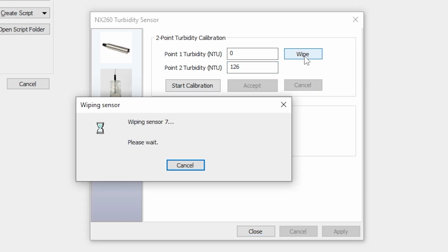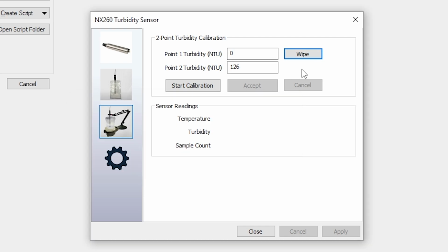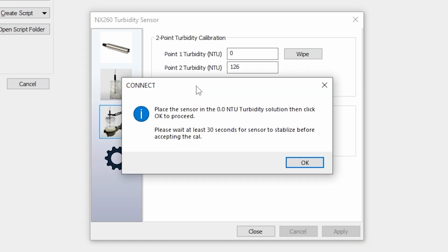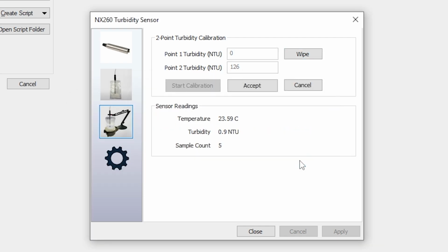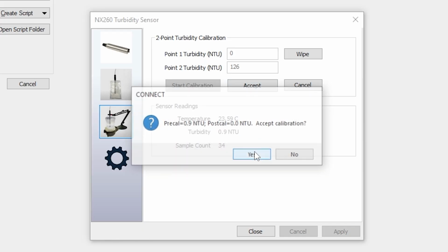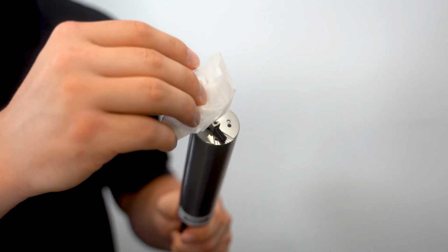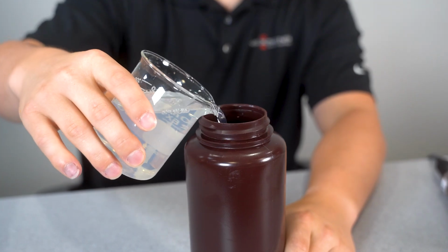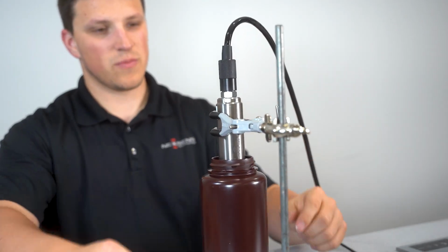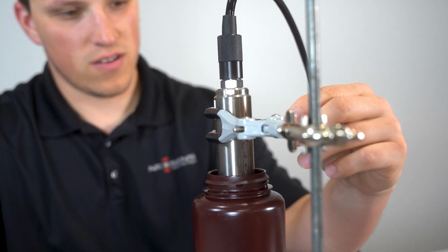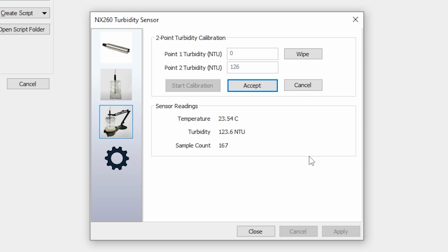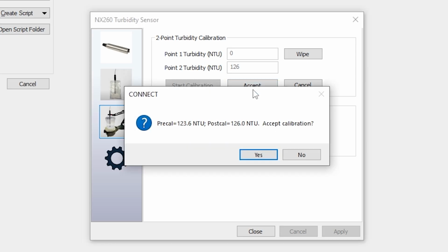Then activate the wiper. Click Start Calibration and wait 30 to 60 seconds for readings to stabilize. Click Accept to store the first point. Rinse and dry the sensor. Place the sensor in a higher reagent, then wipe. Select Start Calibration and allow 30 to 60 seconds to stabilize. Click Accept to store the second point.